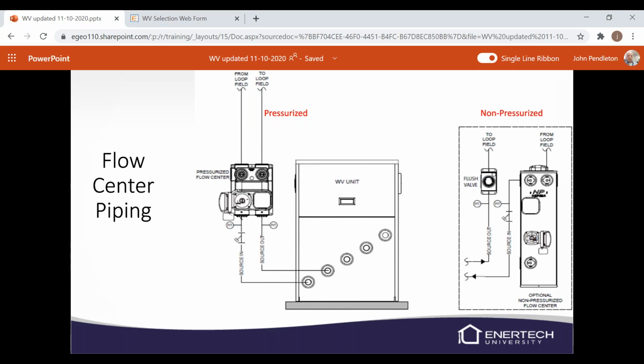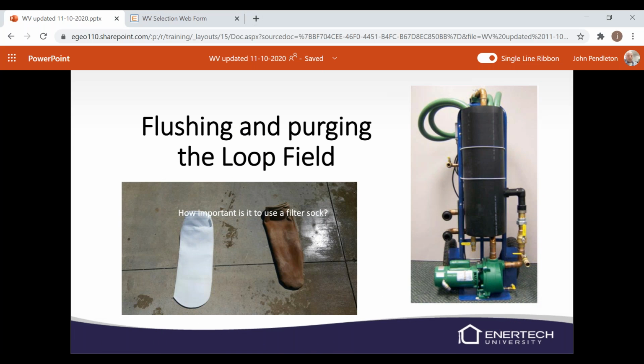Again, we kind of already looked at this. We're not going to hash that out again. I would recommend using a flush cart with these filter socks. You've got a white one and then that brown one. The white one is a 1 micron filter bag. The brown one right there in the picture is a 100 micron bag. So I would start out with the 100 micron, and it just basically goes over the return line on the flush cart, and it'll collect any debris. That's from rust, that brown look to it, rust and debris that was in the system. And these filter socks, they can be washed and reused numerous times.